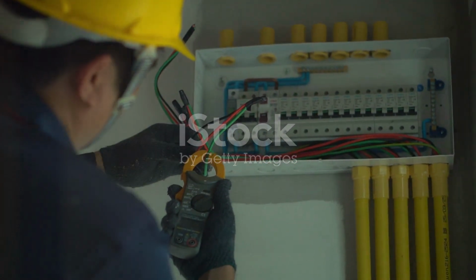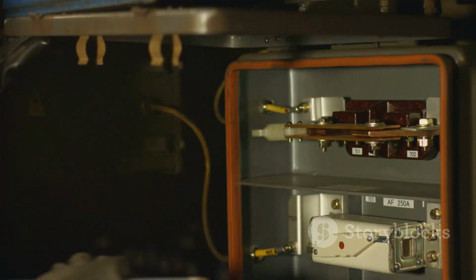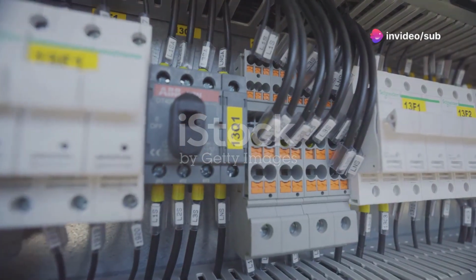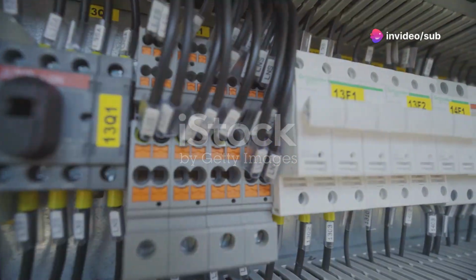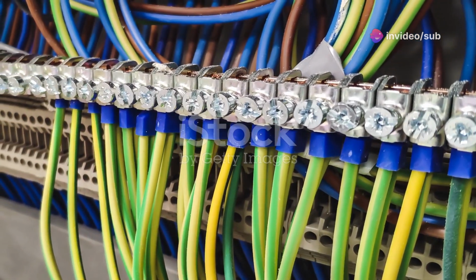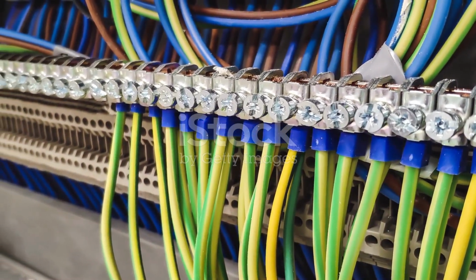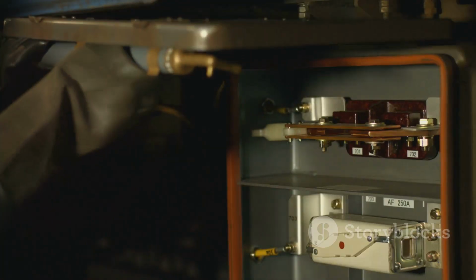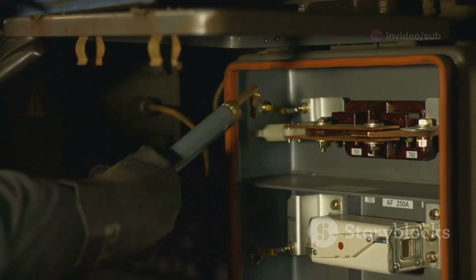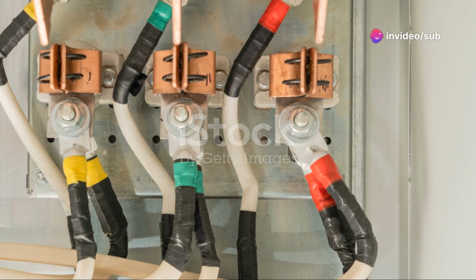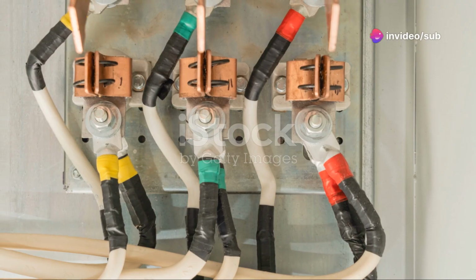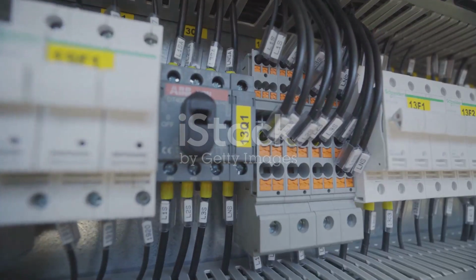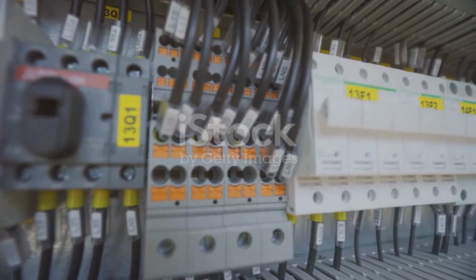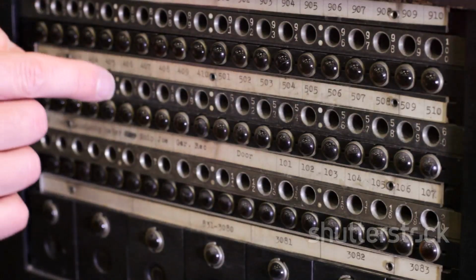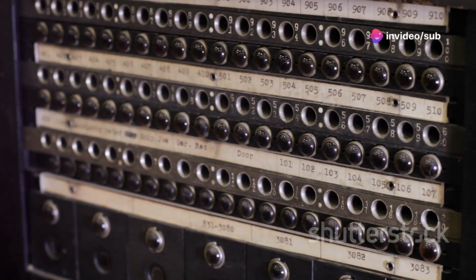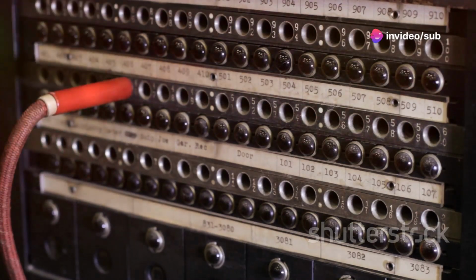Now, let's talk about what happens inside the breaker when there are multiple terminals. All the load terminals on one side are internally linked. This means they're electrically the same point inside the breaker, sharing the same contact and protection mechanism. When current enters the line side, it passes through the breaker's protection device. From there, it splits between the available load terminals, depending on what's connected to each one. The total current can't exceed the breaker's rating, but it can divide among the circuits. If you connect two wires to two separate load terminals, each wire gets the power it needs based on the demand at the other end.